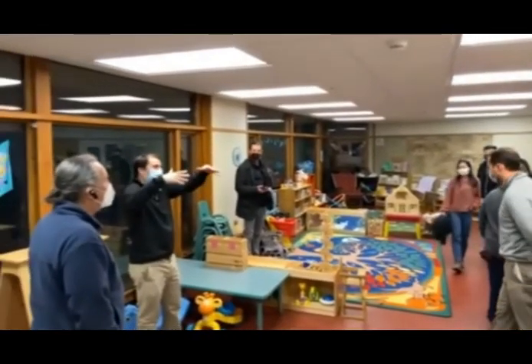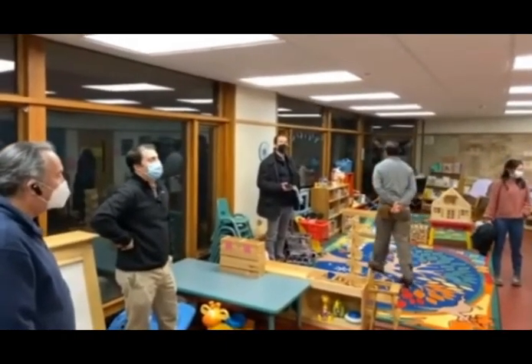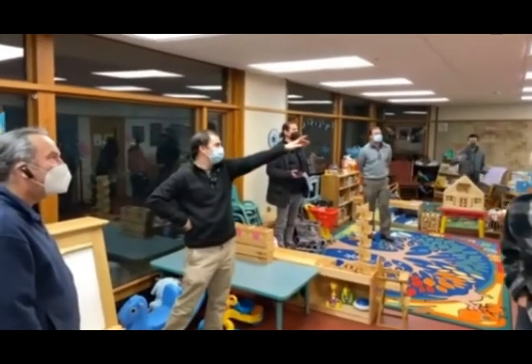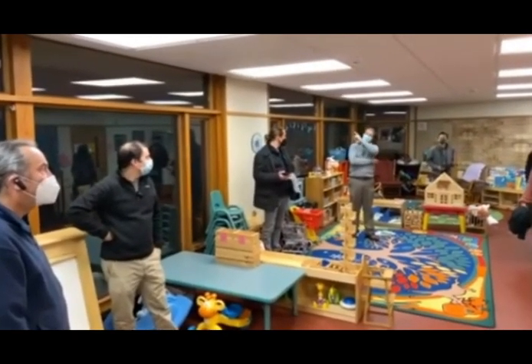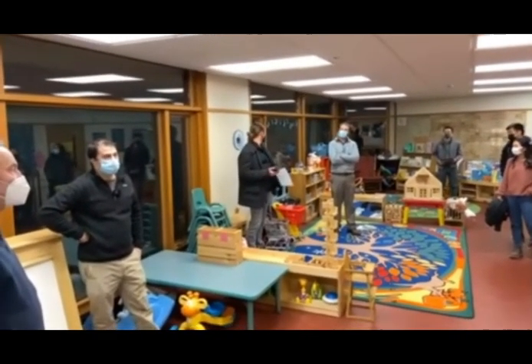So this was the original construction. What year was this? 1989. When I came, all these tiles were bowed. They were so damp, all the tiles were kind of bowing in. I think the picture was taken at one of those return grills. Have you popped up above to see if there's any obvious daylight coming in through the building envelope?